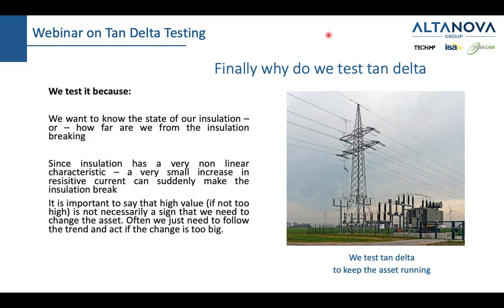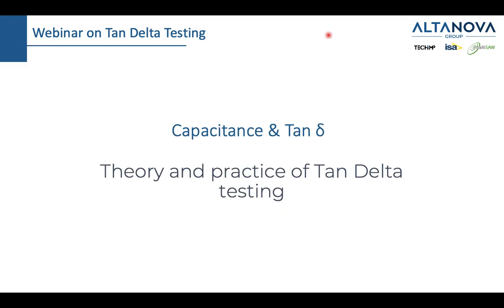So also it's important to emphasize that a high value of tan delta, not too high, and later you will find out what is high, is not necessarily a sign that we need to change the asset. Often what we need to do is simply to follow the trend. And by following the trend, we will also know, do we need to change that asset or not? So another way to answer the question, why we do a tan delta test? We do a tan delta test to keep our asset running. And with this, excuse me, we finished the first part.